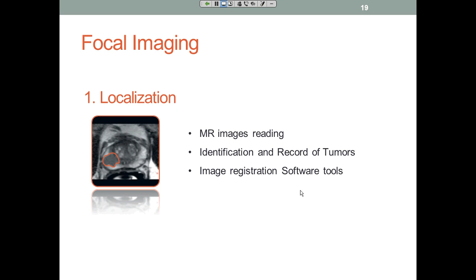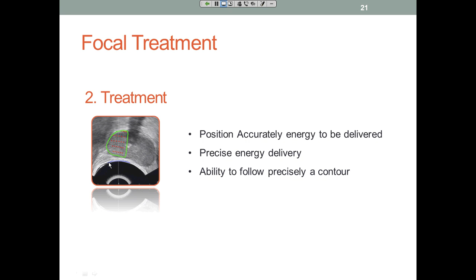There is a system for co-registering the ultrasound image and the MRI image made before treatment. The treatment is also more precise because now the probe allows dynamic steering of the beam. The probe is made of 16 annular rings, allowing precise focusing at different depths inside the prostate. So here again, you can see the volume that the urologist decided to treat, and the machine will position automatically the different focuses that it should scan in order to treat this volume. So now with this dynamic focusing, it really allows to follow precisely a contour.